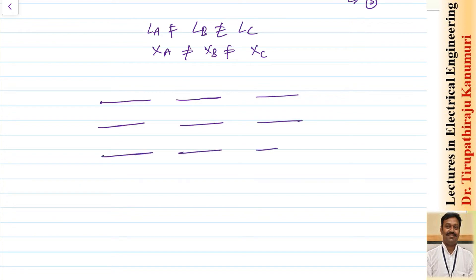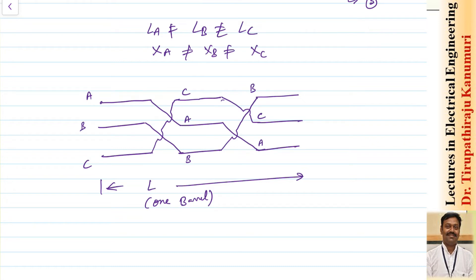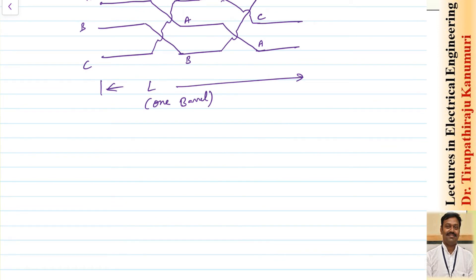For transposition, assume a total length L divided into three equal parts. Conductor A occupies each of the three positions for one-third of the total length, and similarly for conductors B and C. This is called one complete barrel. Because each conductor occupies each position for one-third of the length, the inductance of each conductor becomes the average of La, Lb, and Lc.